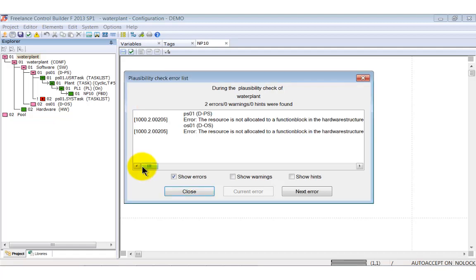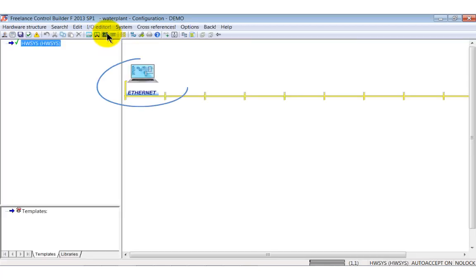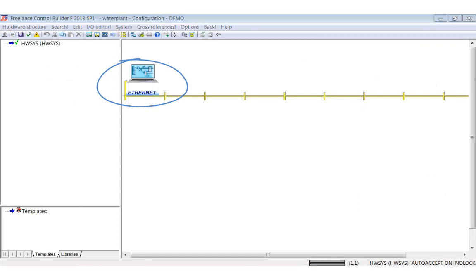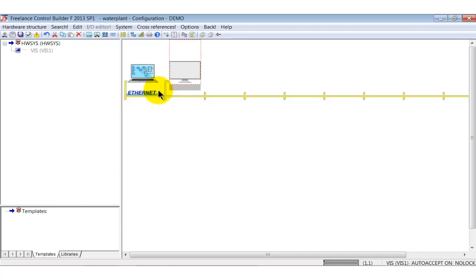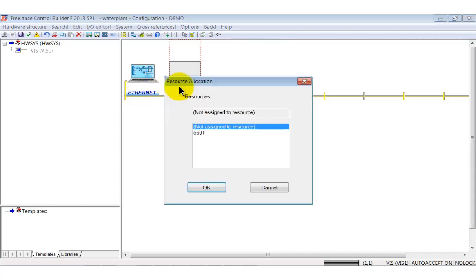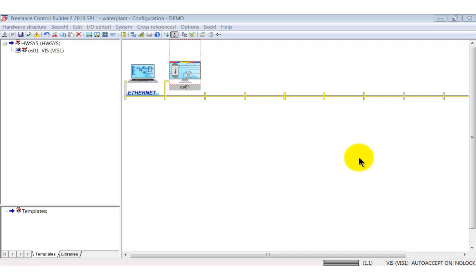These are due to the fact that we haven't allocated resources for the operator station and the process station. Up to now they are only part of the project tree. To perform the resource allocation open the hardware structure. In the new window only an engineering station symbolized by a laptop and an ethernet connection are shown. Right click into the area right to the laptop and select insert operator station. Another PC is added to the hardware structure. Double click the gray rectangle and select OS1.